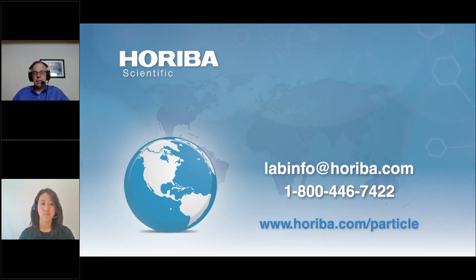The third is that you might use an orthogonal technique to confirm that your sizes are in the same range. I mentioned microscopy before, and my comment there is, if you do two particle analysis techniques and you're within, say, 10 to 15% of each other, that's good. If you do two particle size analysis techniques and they're within 1% of each other, something went very wrong, because it doesn't happen with anything except narrow spherical standards. So keep that in mind as you compare techniques.